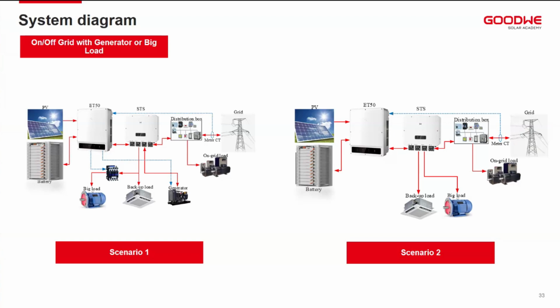Now in scenario two, we have instances where the client doesn't provide or is not prioritizing connection of a diesel generator, but then the diesel generator port of the STS can still be configured to handle big loads.